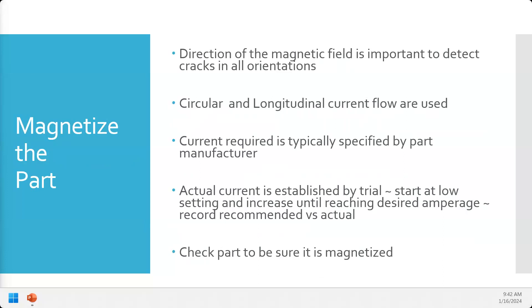Current is directly related to voltage and resistance — V equals IR. Different size and material parts, when placed in the machine, are going to have different resistances. A knob setting of five with one part gives one current, but the same setting with a different part gives a different current. Even two essentially identical parts may have slightly different resistance, or how well you clamp the part in changes total resistance. So you have to play with the dial to get the required amperage.